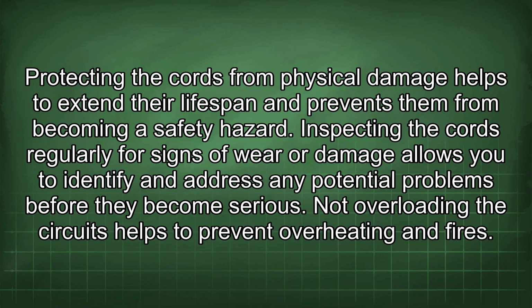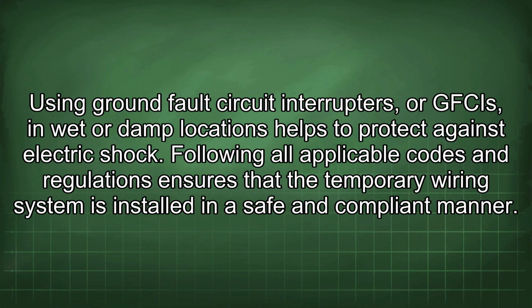Protecting the cords from physical damage helps to extend their lifespan and prevents them from becoming a safety hazard. Inspecting the cords regularly for signs of wear or damage allows you to identify and address any potential problems before they become serious. Not overloading the circuits helps to prevent overheating and fires. Using ground fault circuit interrupters, or GFCIs, in wet or damp locations helps to protect against electric shock. Following all applicable codes and regulations ensures that the temporary wiring system is installed in a safe and compliant manner.